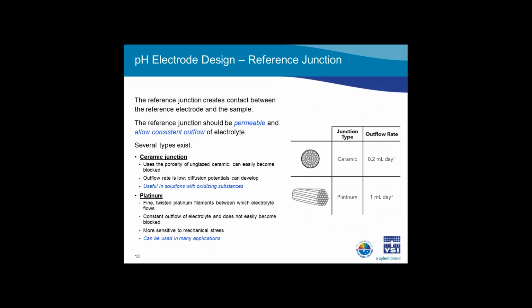As was previously mentioned, the reference junction, sometimes referred to as a salt bridge, creates contact between the reference electrode and the sample. Like the reference electrolyte, the junction needs to have certain qualities. It must be permeable and it must allow a consistent outflow of electrolyte. Now I do want to mention that there is a variety of junctions offered by manufacturers, but we will discuss the most relevant YSI junctions.